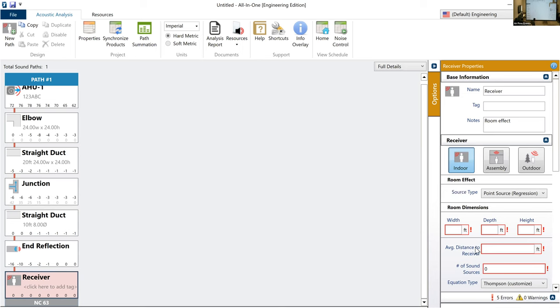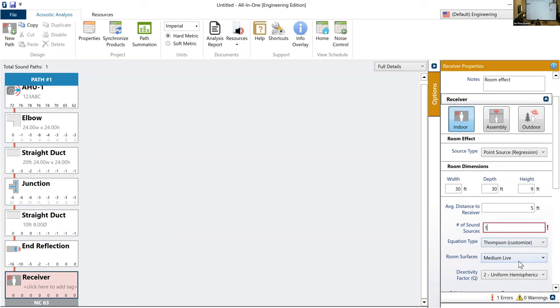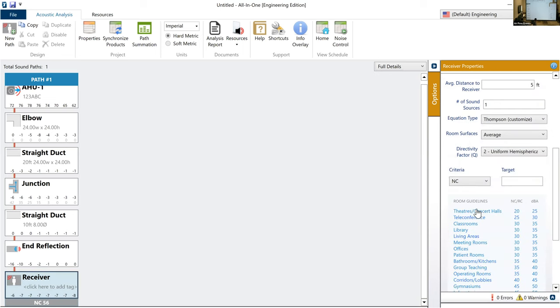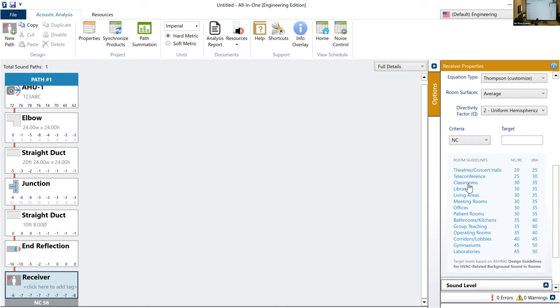And at that point, we can model the classroom space. Again, modeling the size of the room, if you wanted to do a theater space like this, you could do that with the size, width, depth, height, average distance to receiver. We'll say 5 feet, as in someone sitting directly below the actual diffuser. And then you can say, what is this space constructed of? Is it live? Is it dead? We're going to use average maybe for a classroom. Once you get down to that, it'll ask you, what is your criteria? And this is important. So what do we want the background sound level of a classroom to be? If you're not familiar, there's actually a great reference from ASHRAE right here. Classroom, that sounds good.